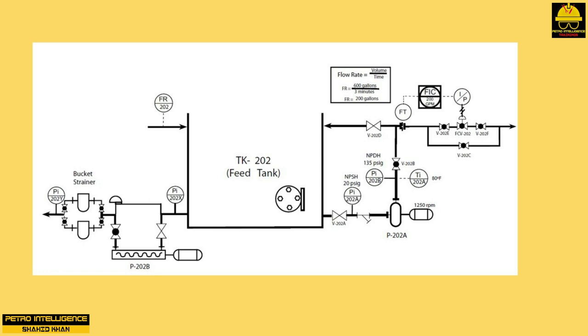Look at tank levels. 5. Open pump suction line and pump vent valve to liquid fill, prime the pump. Be sure all of the valves between the pump and the tank are open. 6. Crack open pump discharge valve.